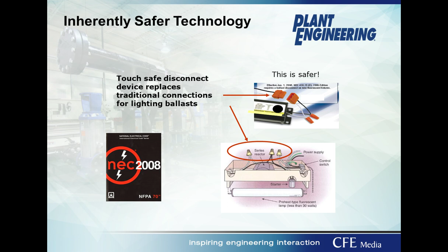That was the challenge being faced prior to this requirement: too often people were making the decision to disconnect the twist-on wire connectors, as we see in the lower right photograph, without de-energizing the circuit, just being very careful not to touch anything energized. That works a lot of times. Unfortunately, for a number of electricians, it did not work. So the touch-safe disconnect is an example of inherently safer technology.